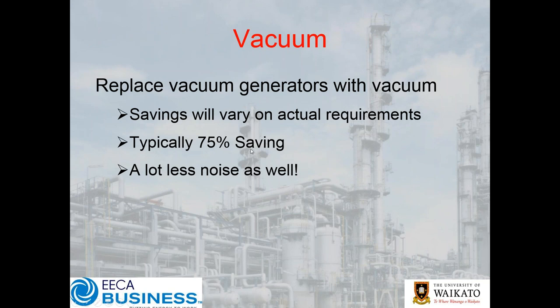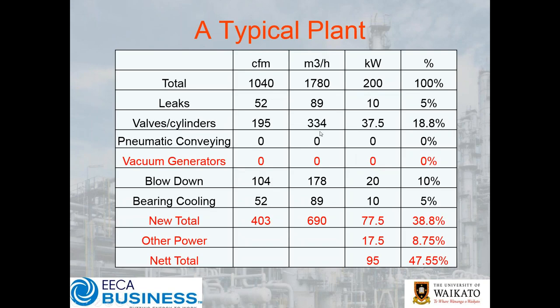Let's take a minute to talk about vacuum. There are plenty of compressed-air-driven vacuum generators on the market. As a typical rule of thumb — depending on the level of vacuum you need to generate — your typical savings are in the order of 75%. The added bonus with new health and safety legislation is you may be able to sell this on safety grounds: you've got a high level of ambient noise and the best thing you can do is drop that noise. What we're going to do is eliminate compressed air being used to generate vacuum and introduce a dedicated vacuum system — you'll notice air use drops substantially, with a minor increase of 5 kilowatts in other power used.